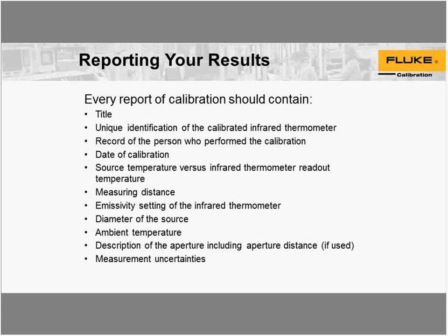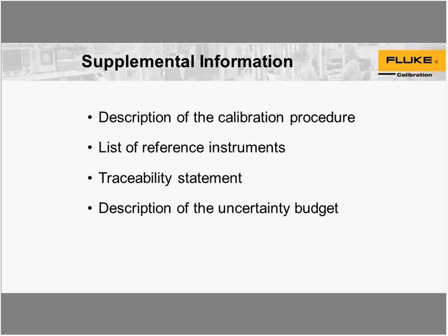When reporting results, your report of calibration should contain the following: the title; identification of the calibrated infrared thermometer such as model number and serial number; a record of the person who performed the calibration; the date of calibration; a record of the reference temperature versus the infrared thermometer readout temperature; measuring distance; specific settings of the infrared thermometer; diameter of the source — specifying your calibration geometry so the customer knows how you calibrated it; the ambient temperature of the laboratory; a description of the aperture if used and where it was in the calibration geometry; and the measurement uncertainties for that calibration point. You also want descriptions of the calibration procedure, reference instruments, traceability statement, and a description of the uncertainty budget.